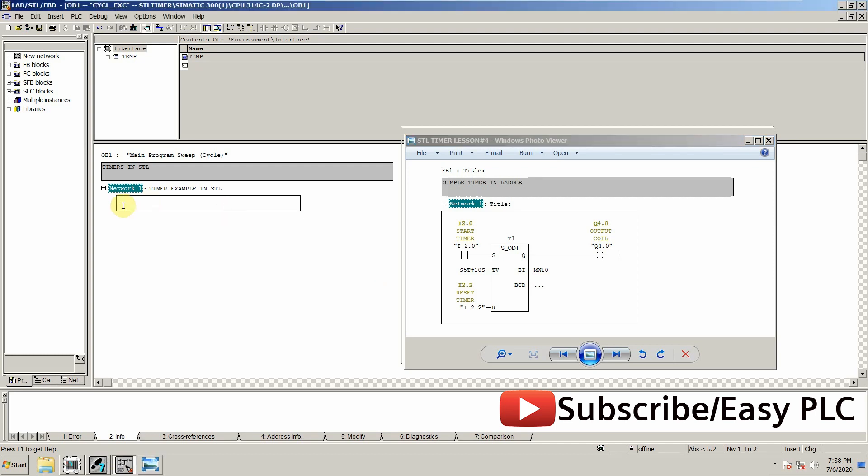First of all we have to enable the timer T1, so it can be enabled using an input. First we will use AND operation and I2.1. FR command is used to enable a timer, so FR T1.